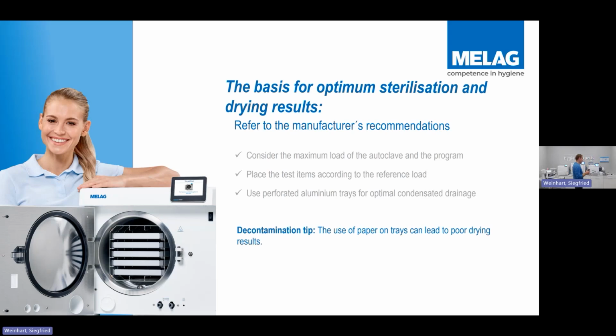Sometimes I see it with practices, they'll put paper down on these trays. It's important that we don't have paper on those trays, because if you imagine when that is in the chamber itself, okay, and if you have paper in those trays, you restrict the amount of drying. Because what can happen within the sterilizers is the air, the steam, and even the drying will circulate around that internal chamber. So it's either coming up through the trays, or it's going down through the trays, very much dependent on the manufacturer.